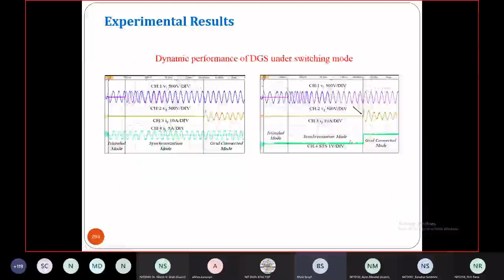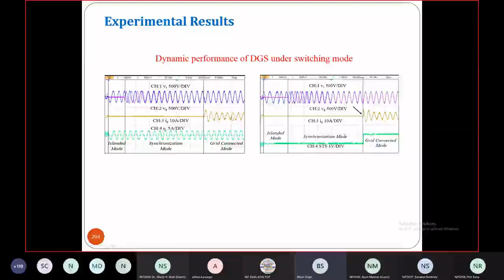Now, this system - grid is there, grid is not there. So grid synchronization - this is typical grid synchronization. You can see load voltage and load current are there, and grid appears here. After a few cycles it synchronizes to the grid, and grid current starts flowing after synchronization, as clearly shown here. And when the grid disappears, the system still works very well without much problem.